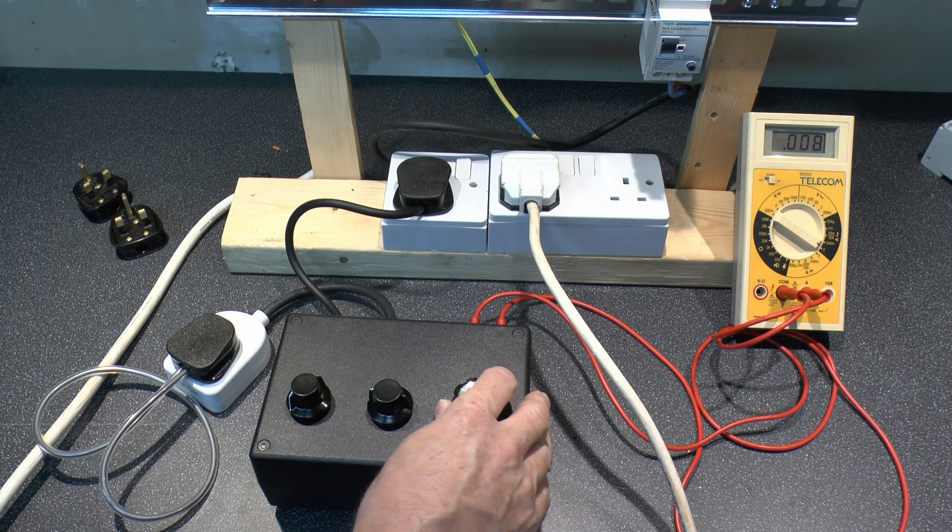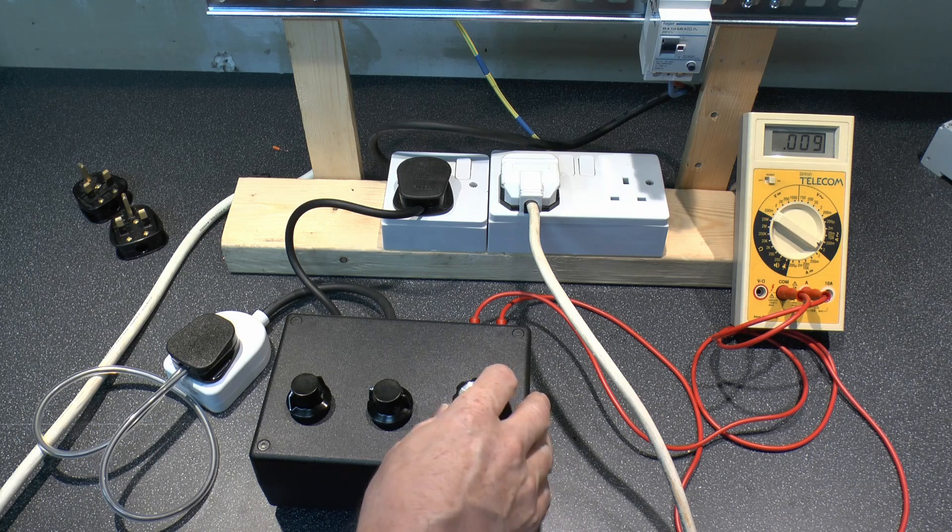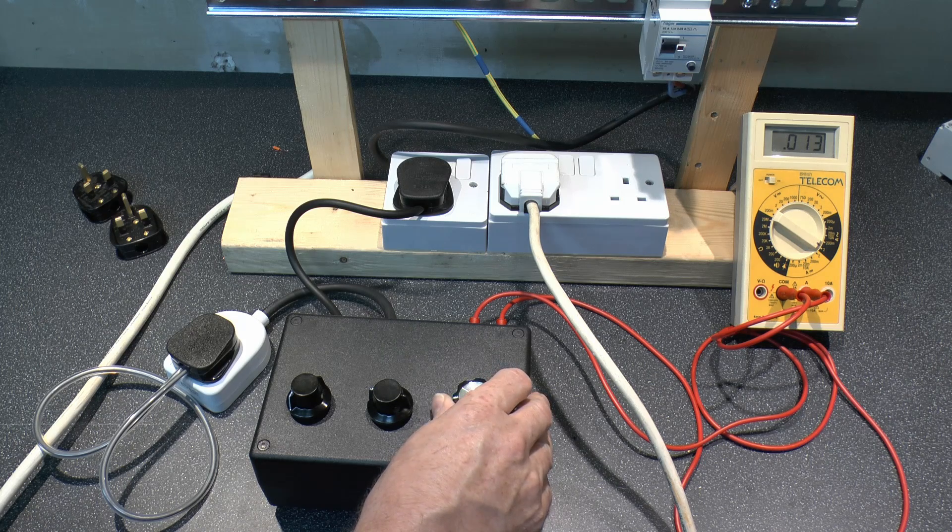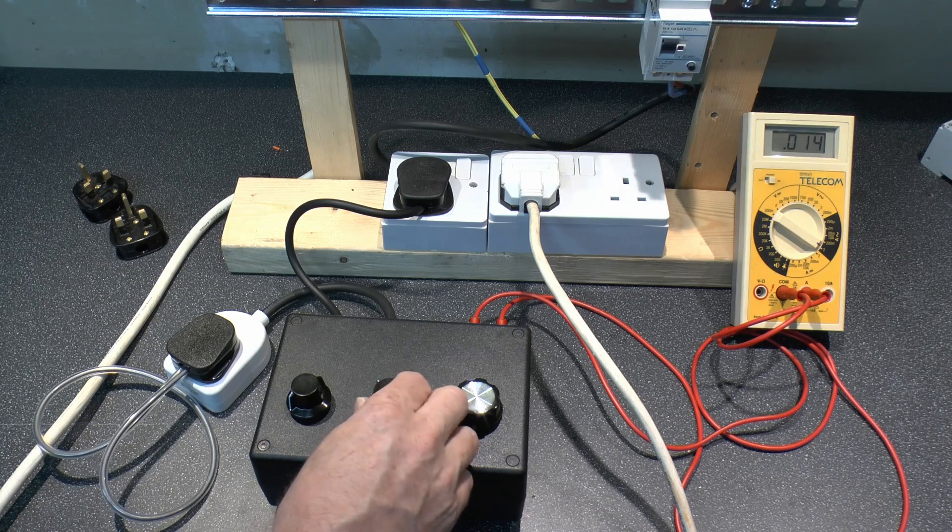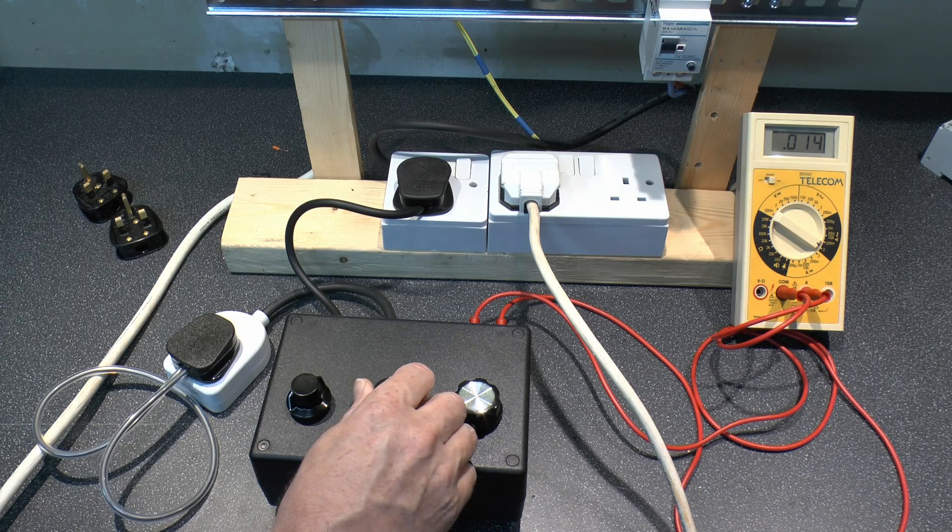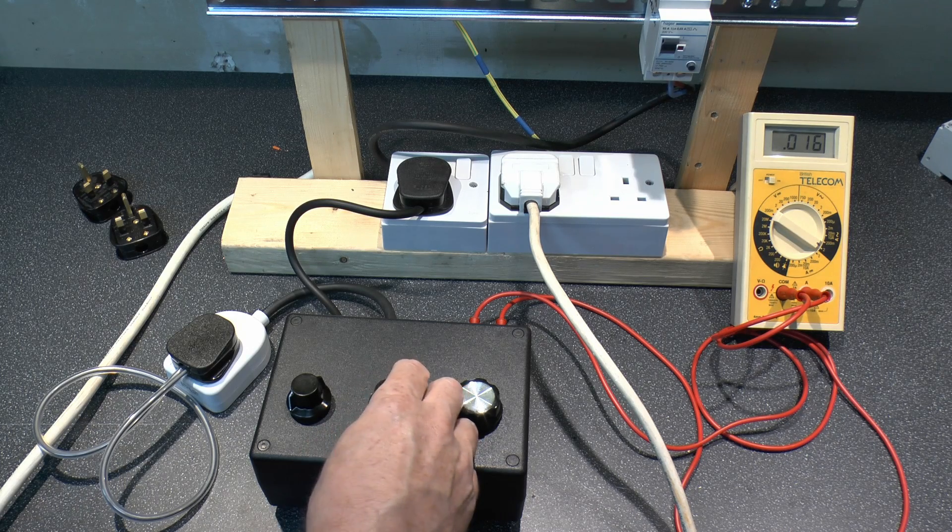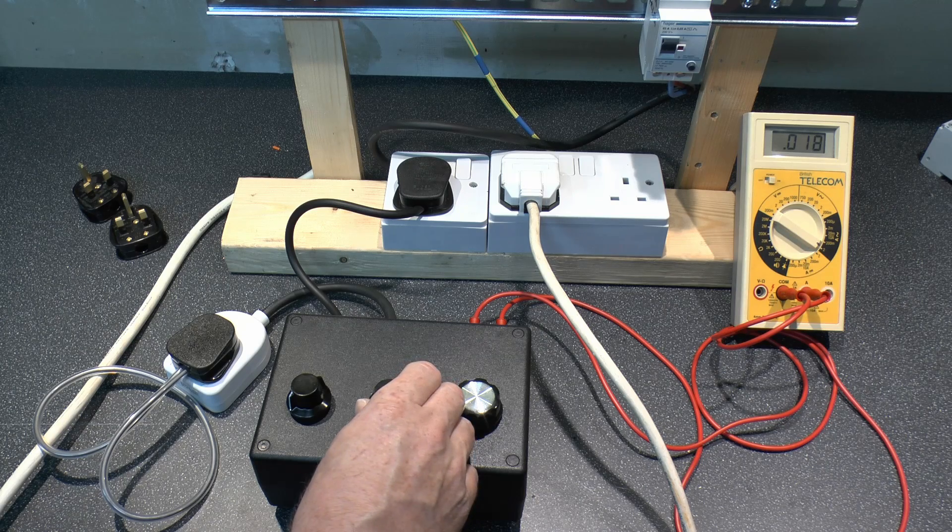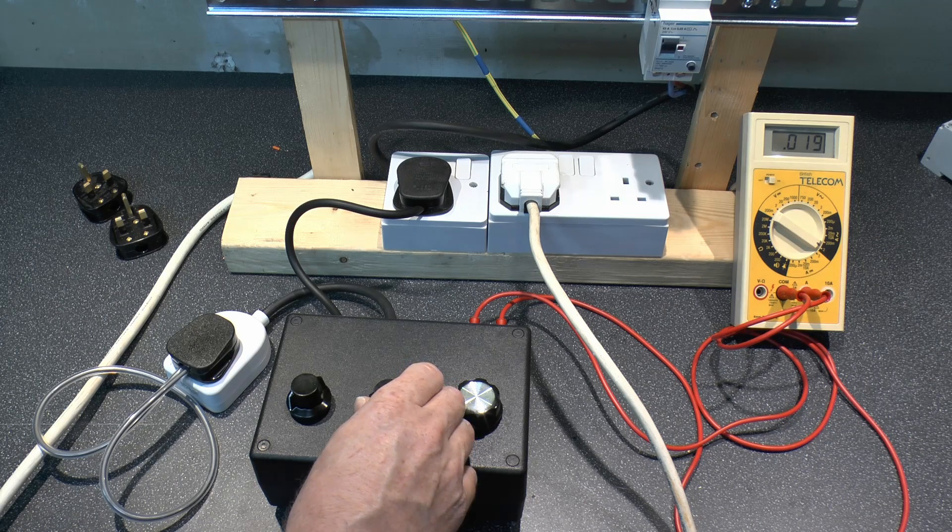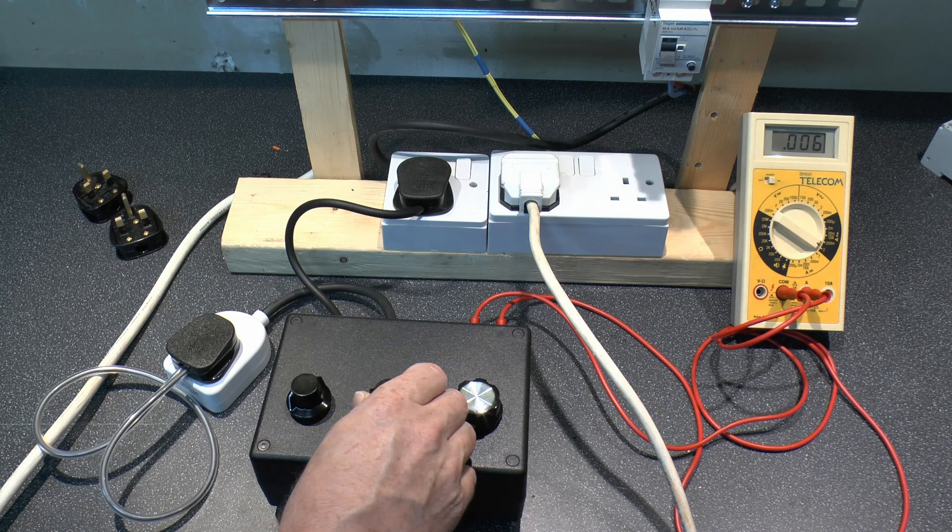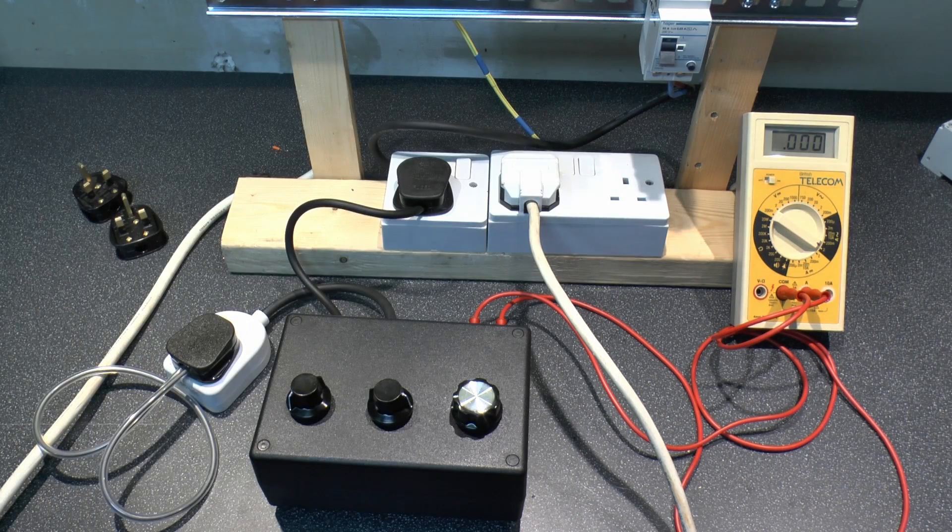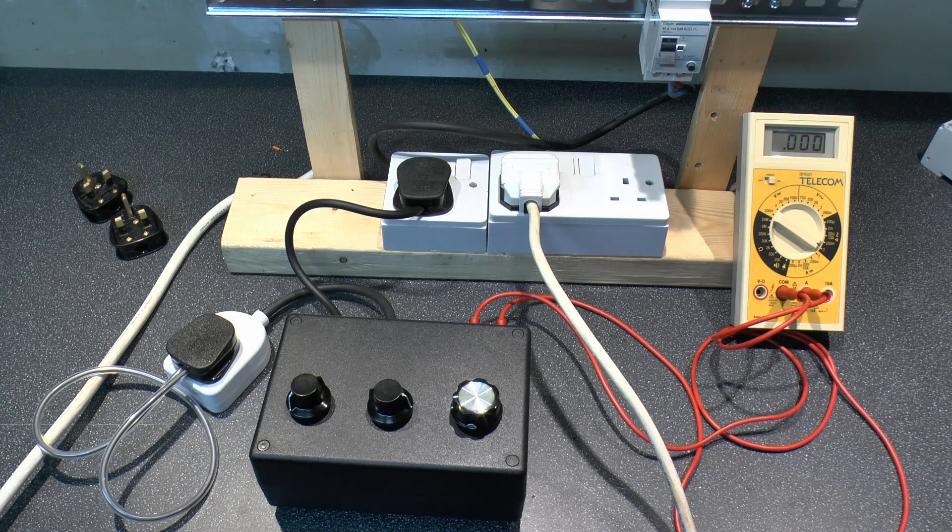So current increasing away there so 10, 11, 12, 13. I've gone to the second knob there. So 16, I believe it was about 21 so it should trip any moment. Okay so that was 21 again so again consistent with what we had previously.